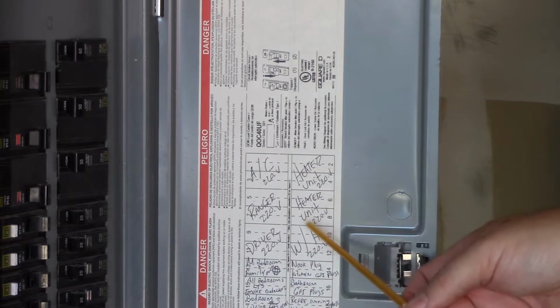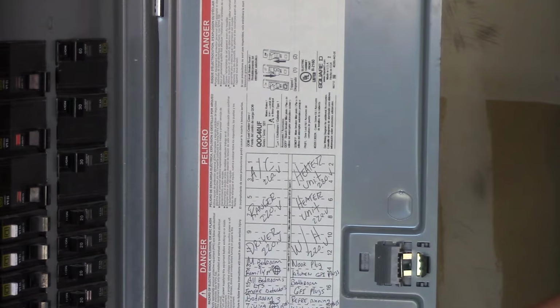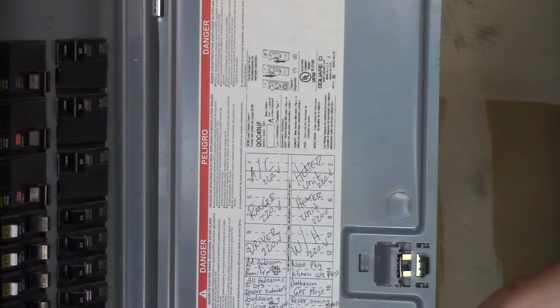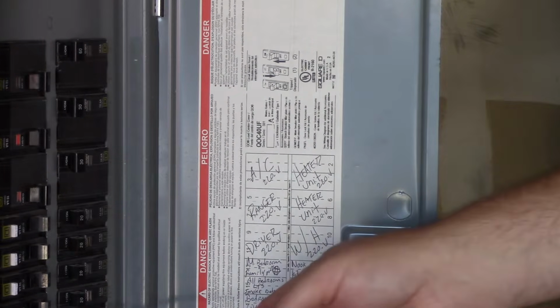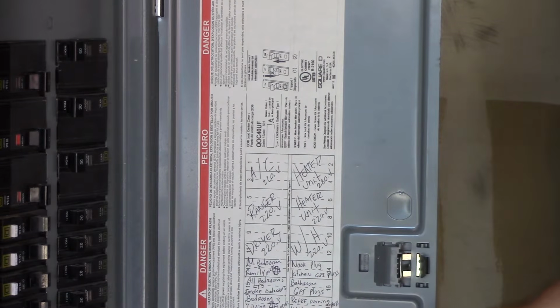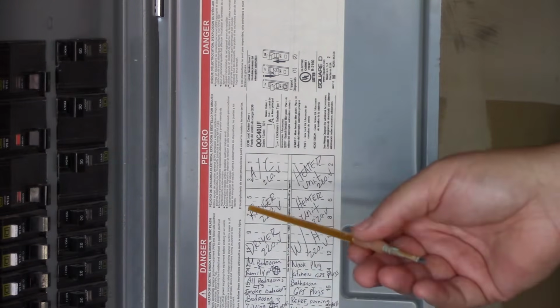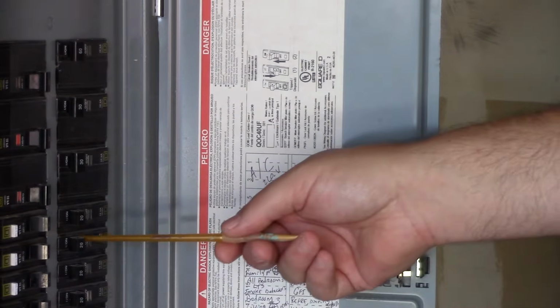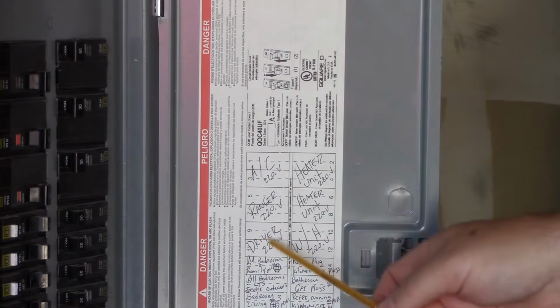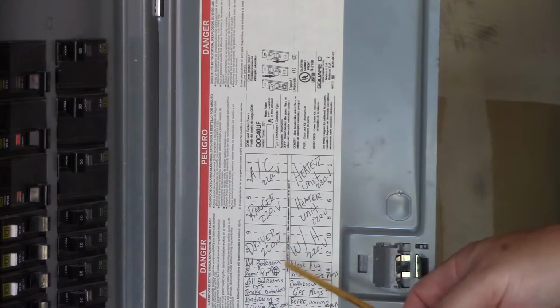All right, so here we go, and we're looking down here, and everything looks in order. One of the things we look for is to make sure that it corresponds with the size, so we know that the kitchen is a 20 amp breaker, so that looks like they're good with that. So far, microwave at 20, looks like it's dedicated on its own. Here's a disposal and dishwasher, obviously being put on a 20 here. And you've got the washing machine. So everything in here looks okay as far as how we look at the legend. Now in this case, this legend is detailed enough that I know which circuit breaker is associated with this different number that's on this actual cover. So that part we're okay.